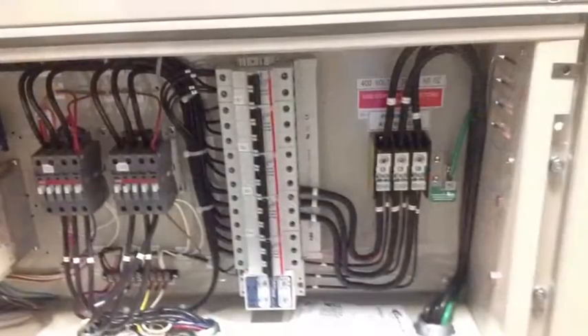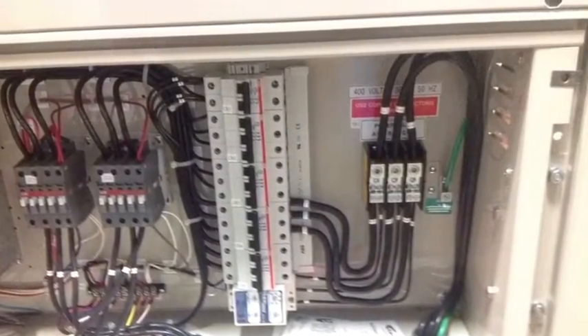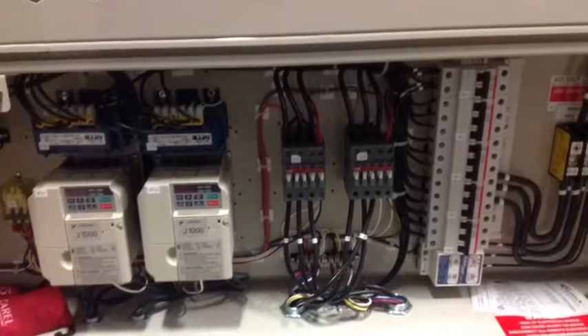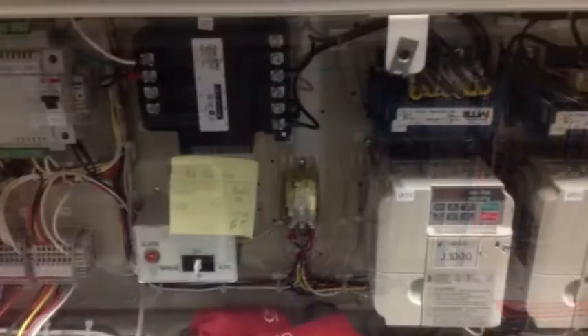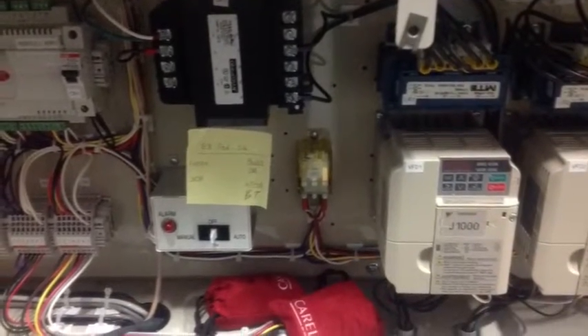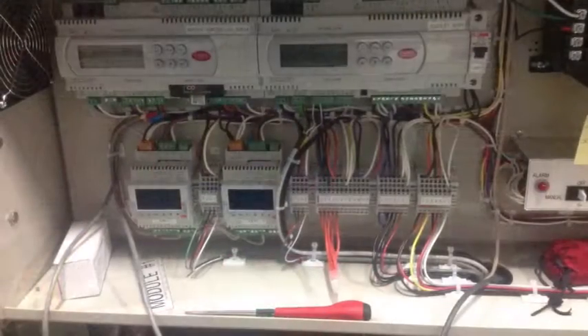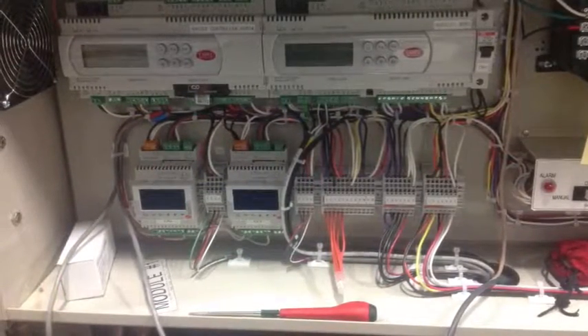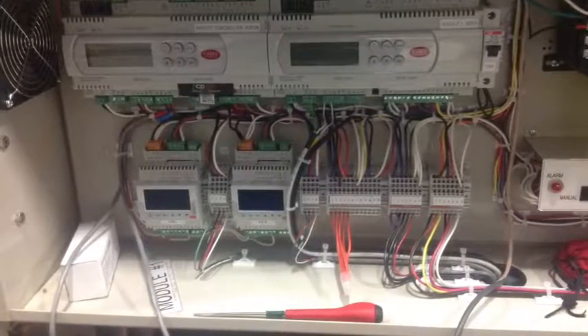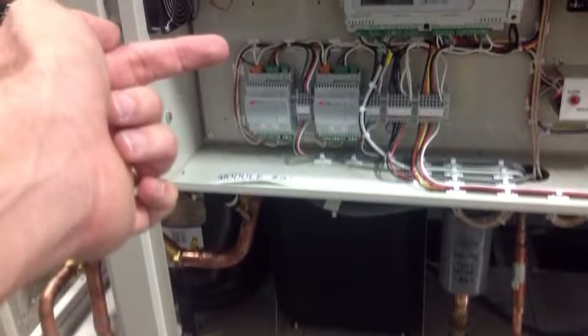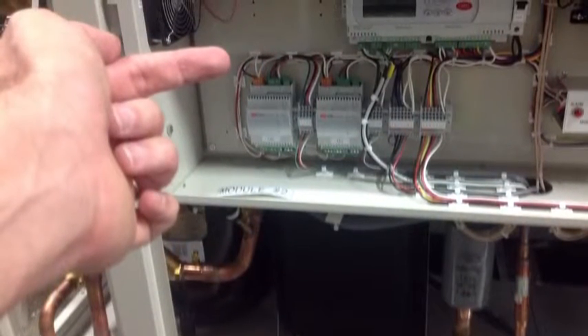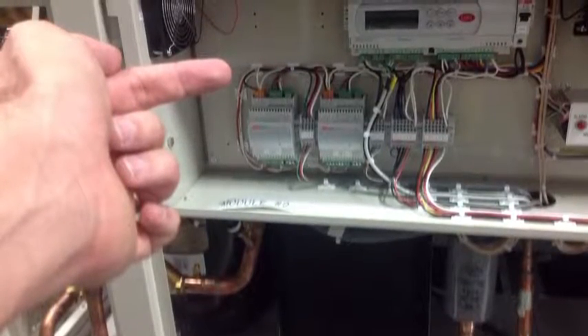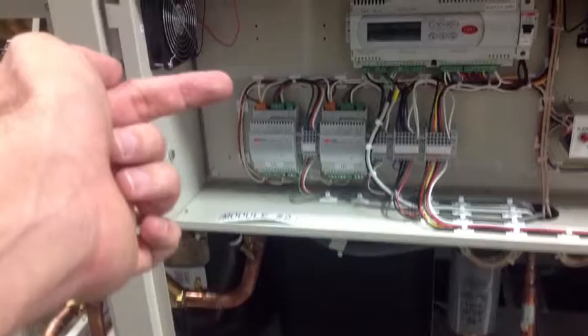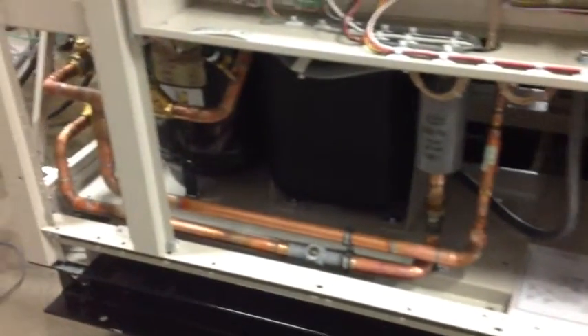Now as we work our way right to left, we see incoming power go into 5 sets of circuit breakers. 1 for control power, 1 each for condenser fans, and 1 each for compressors. The gray compressor contactors, the Yaskawa VFDs for the condenser fans, a control power transformer, the manual off-auto switch, and again the Carel Pico controllers. My finger is pointing to the open spot on the slave module. It's a slave module because it only has 1 pCO controller. The mechanical master module has 2 of those controllers, 1 for the module itself and 1 to govern the operation of all 7 mechanical modules. Now we'll scan right to left underneath the control panel, seeing the 2 compressors, the evaporator, and the receiver.